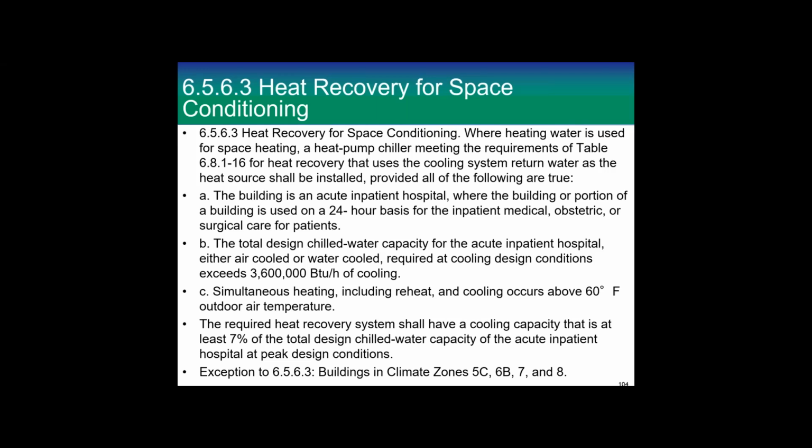But what we're doing is, hospitals have strong humidity requirements, and they are often in reheat. And so the simultaneous heating and cooling for hospitals is tremendous. They're always heating, they're always cooling at the same time. So this is a very good thing if you're in healthcare.